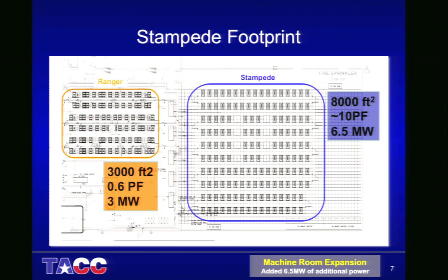And in contrast, this is what we're looking at with Stampede. This is the wall that I mentioned got torn down. So all of this part on the right is new. And it has a very big footprint. Part of the reason it has such a big footprint is because we designed it to be able to take 2 of these large Xeon Phis, or it could take 2 large GPUs. And that increases the footprint of the system pretty dramatically. So we went from 80 racks over here to about 160 compute racks on the right-hand side. It is about 10 petaflops peak, as I said. And we had to add new power. So we delivered about a new 6.5 megawatts of power into this facility. And this just went offline, and this has been online for about 2 months.